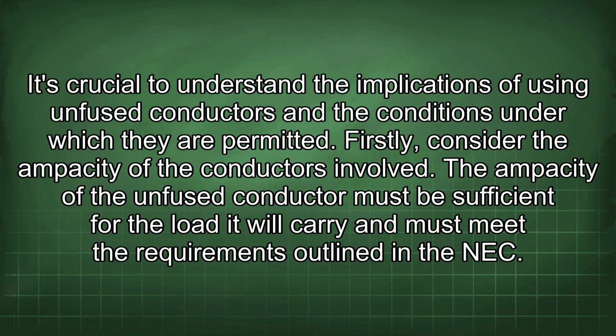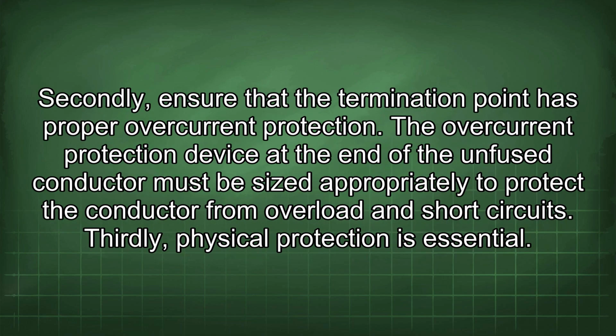It's crucial to understand the implications of using unfused conductors and the conditions under which they are permitted. Firstly, consider the ampacity of the conductors involved. The ampacity of the unfused conductor must be sufficient for the load it will carry and must meet the requirements outlined in the NEC. Secondly, ensure that the termination point has proper overcurrent protection. The overcurrent protection device at the end of the unfused conductor must be sized appropriately to protect the conductor from overload and short circuits. Thirdly, physical protection is essential.